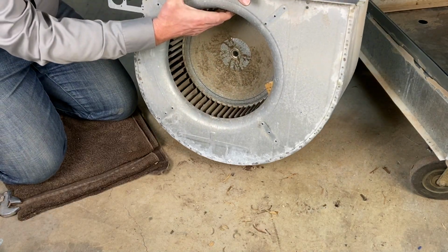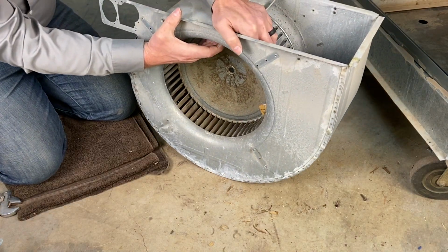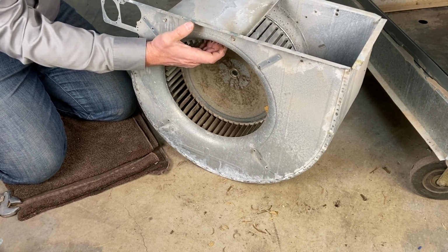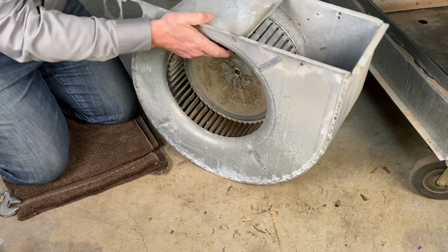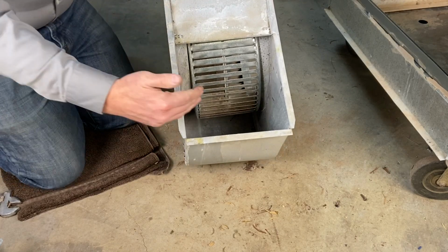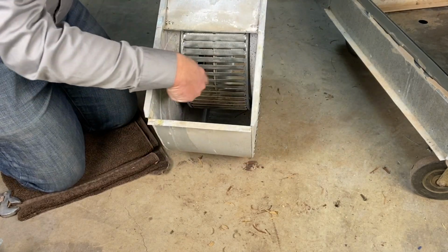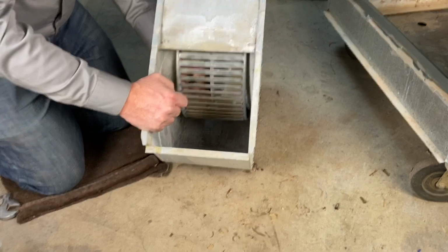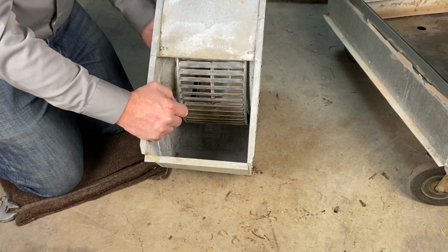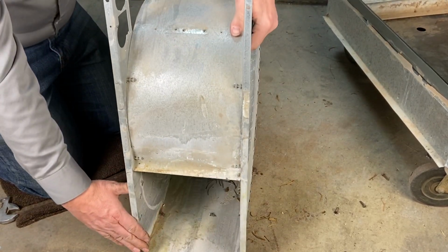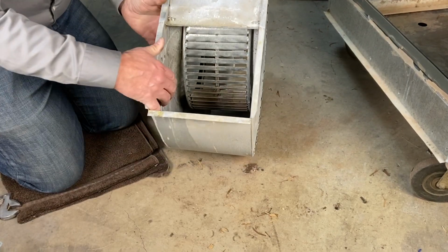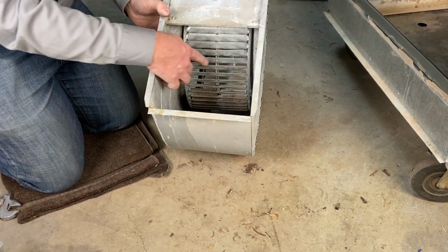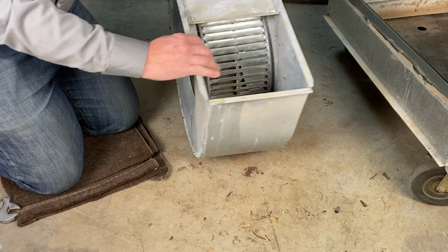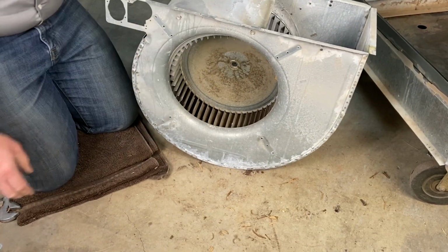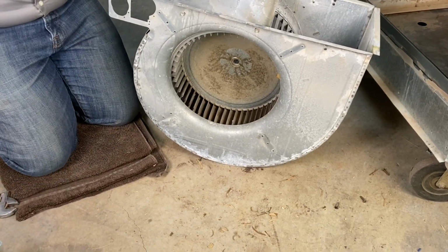So this blower wheel is really dirty. What I would do in maintenance is take this out and clean it. When I take it outside to clean it, I would take a water hose and spray it down at this angle and spray every single fin while turning it by hand. I would dump the water out, and then wash it again. And I'd wash it over and over and over until I got all of these fins clean. What we're going to do is go ahead and take it out of the housing so we can see it entirely.